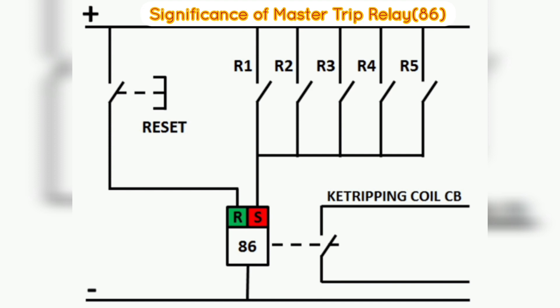Second, the use of a Master Trip Relay reduces the complexity of wiring. If the Master Trip Relay is not used, then we have to wire all trip contacts of the protection relays directly to the circuit breaker's trip coil. The output of the protection relays is 110 volts DC, and thus DC voltage routes into the breaker for each protection relay, increasing chances of DC voltage leakage. This reduces the reliability of the protection system, and a lot of wiring causes more cost.